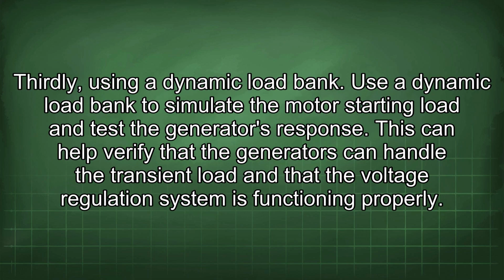Thirdly, using a dynamic load bank. Use a dynamic load bank to simulate the motor starting load and test the generator's response. This can help verify that the generators can handle the transient load and that the voltage regulation system is functioning properly.